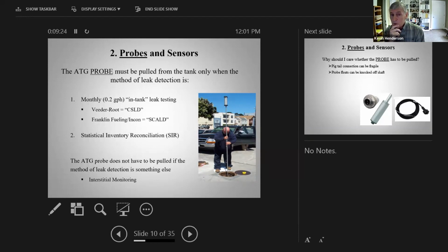When do we have to do this? When does the probe have to be pulled out of the tank? The only time it has to be pulled out of the tank for the operability testing is when you are doing 0.2 monthly leak testing, or you're using that probe as inventory for doing SIR. So if you're doing something else to meet the leak detection requirements, maybe you're doing interstitial monitoring on everything, there is no reason to pull the tank gauging probe. But if you do 0.2 monthly testing or SIR, then yes, you need to pull the probe and verify that it is actually functioning correctly.